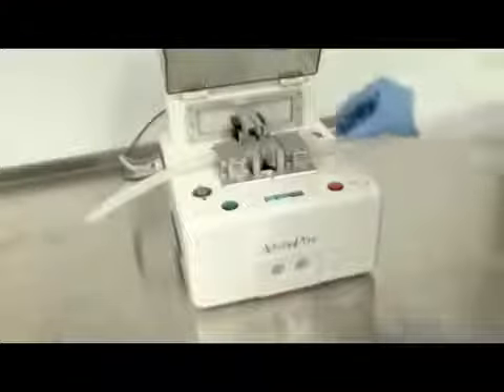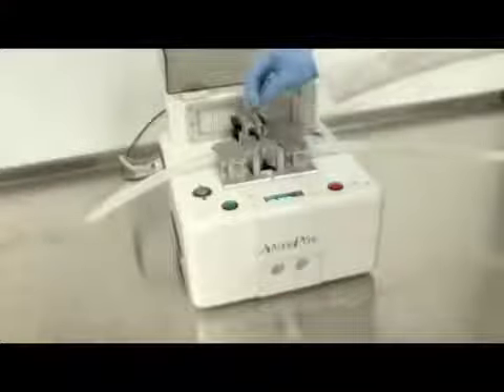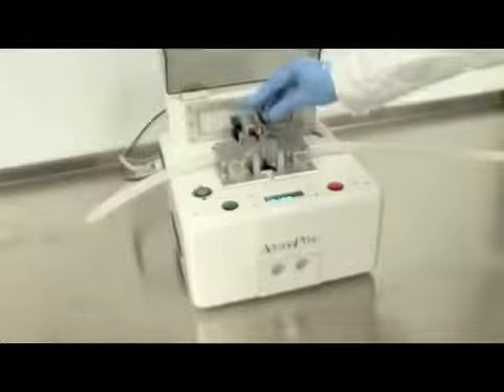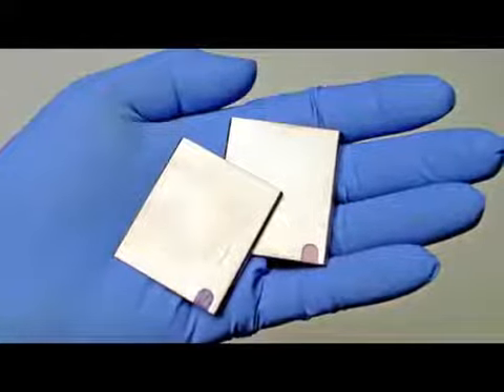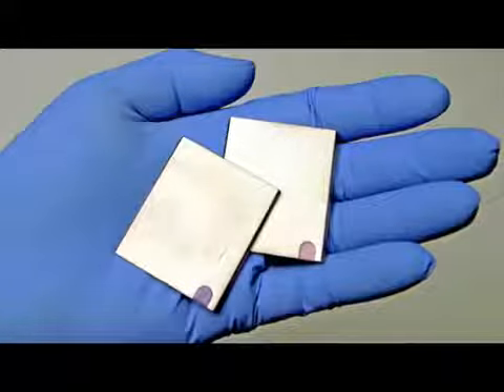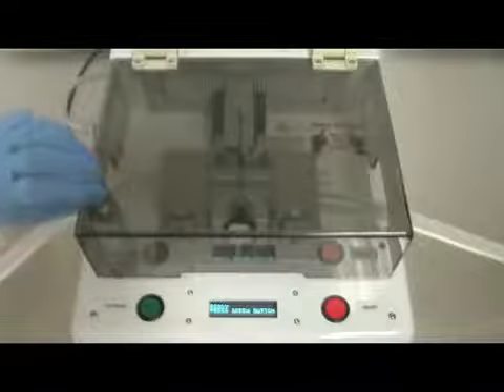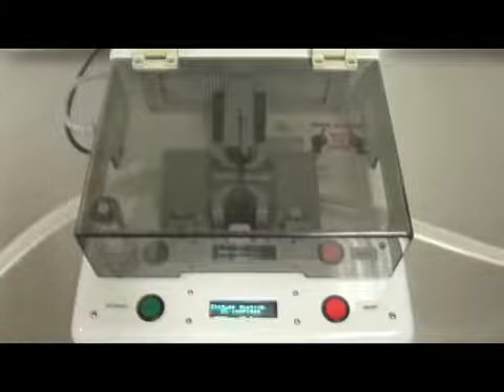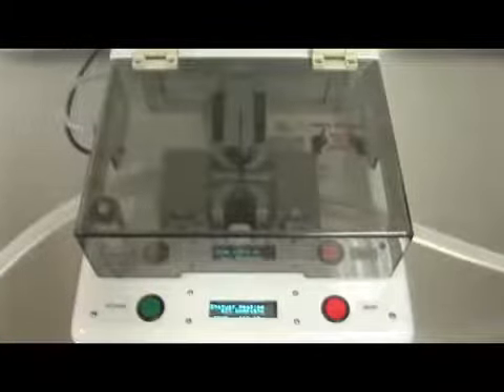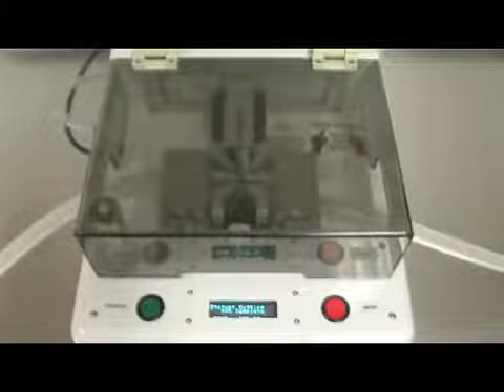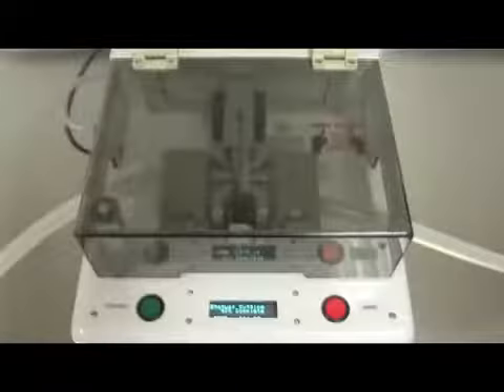A tube cutting blade is inserted into the device where it goes through an initial depyrogenation cycle, sterilizing the blade. All edges on this blade are blunted, making them very safe to use, and have an optical sensing tab that the machine scans, ensuring single use. Once the cover is closed and the cycle initiated, both tubes are pinched shut. The sterilized blade cuts through the tubes.